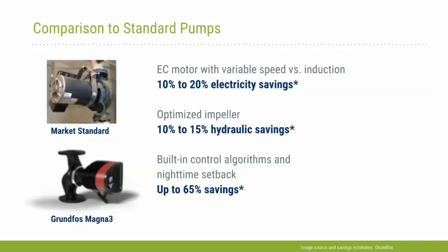Okay, next slide. So just a quick comparison to standard pumps. The energy savings come from a 10 to 20% more efficient motor. You also have a more efficient pump itself, so the optimized impeller gets 10 to 15% hydraulic savings. And then really the big savings comes from the built-in control algorithm. This particular one also has a built-in nighttime setback feature. And you can see the savings estimate from the vendor is up to 65% for this particular pump.